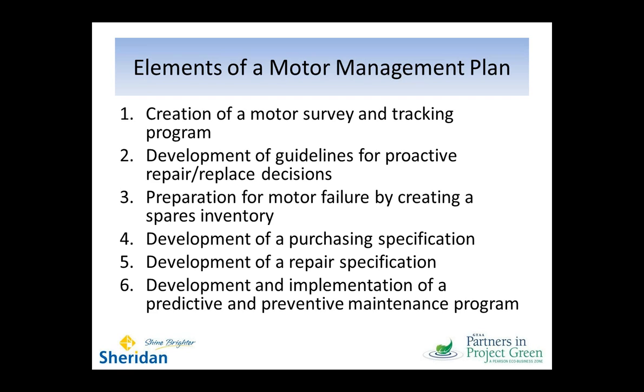You have to also get to the point of determining whether a motor should be repaired or replaced, and I also cover a bit of the tool for that. And finally, you've got to develop and implement a bit of a predictive and preventive maintenance program. So this gives you a chance to keep that motor inventory you've got in good shape for a longer period of time.